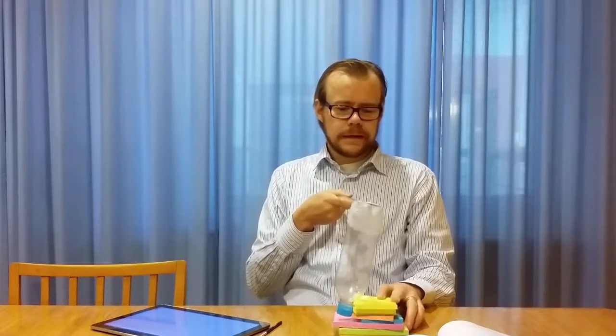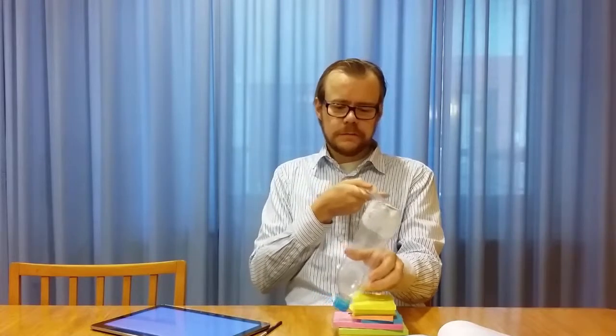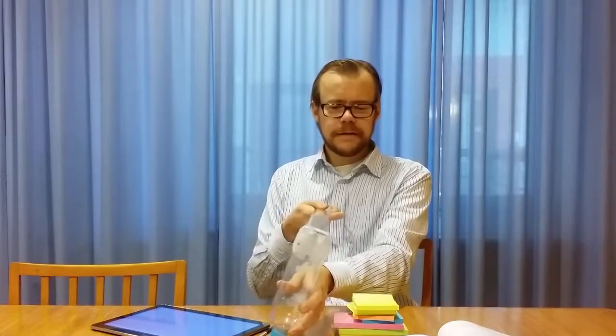The problem arises when, let's say I change the viewing direction for you, and then we view the tip from this way when I scan. And here I scan, and then I come to the object, and then the tip will bend like this a little. So we will have some kind of torsion motion here. And then when it comes over, it snaps back and goes back down. And this is very clearly seen if the sample is sticky and not very hard. Then the tip will have these friction forces against the surface while it scans.